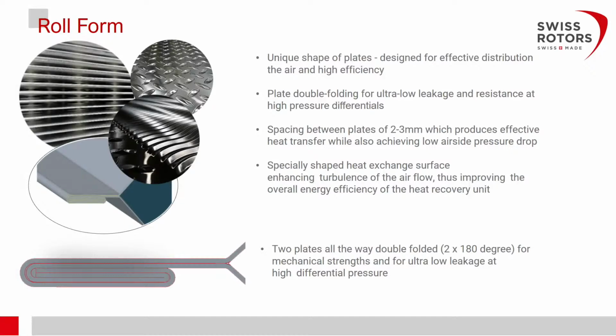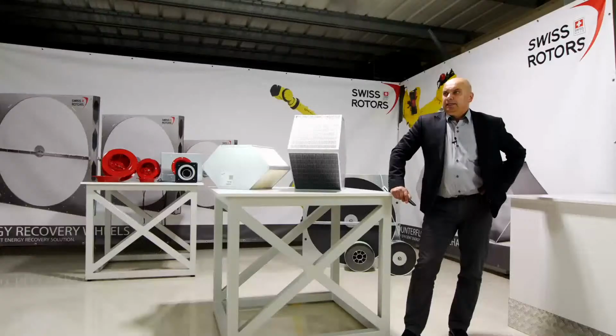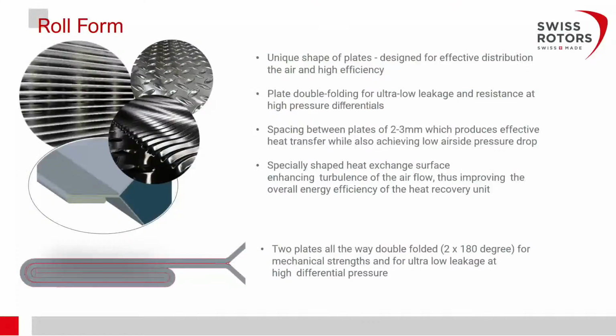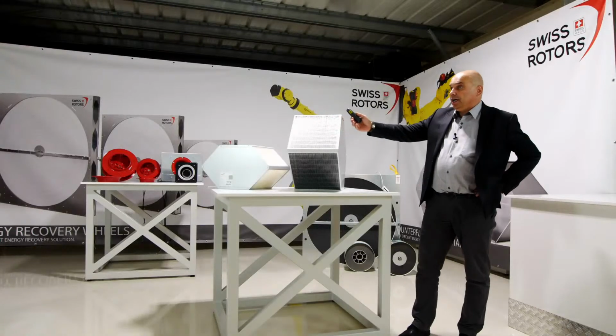So, some information. The shape, as I mentioned, is quite unique, especially designed for higher efficiency and lower pressure drop. The plate double folding gives ultra low leakage and resistance at high pressure differential. Thanks to this double folding, it can stand higher differential pressure. And these two plates, as I mentioned earlier, double folded 2 times 180 degrees, also give higher mechanical strength. So it's not so fragile. The edges are not so fragile like the other ones.